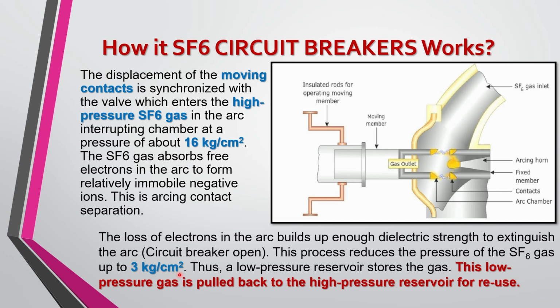Now the question arises how this pressure is again built for the next operation of the circuit breaker. So a low pressure reservoir stores this gas. This gas at 3 kg per centimeter square is stored in a low pressure reservoir, and this low pressure gas is pulled back to the high pressure reservoir for reuse. So there is a mechanism to pull this low pressure SF6 gas into the high pressure chamber with the help of some high pressurizing chamber. So basically 3 kg per centimeter square SF6 gas is converted again into 16 kg per centimeter square pressure gas.